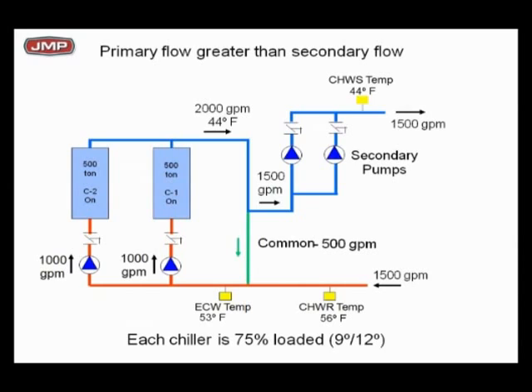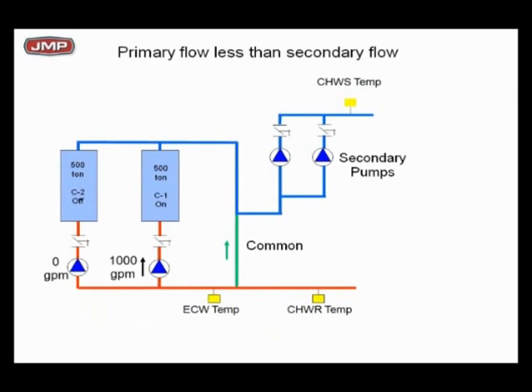There's a 9 degree delta T, 53 degree return, 44 supply, 9 degree delta T, and the design was 12. So I'm 9-12, so each chiller is 3/4 loaded, typical operating condition in the system. How about if our primary flow rate is less than the secondary flow rate? Let's just take a look. What am I going to do here now?